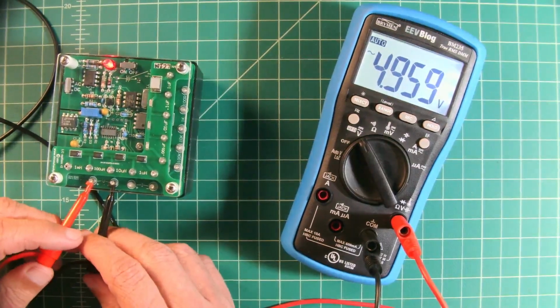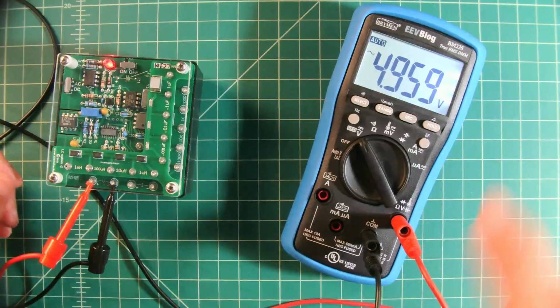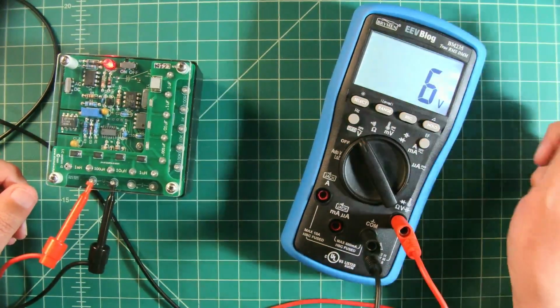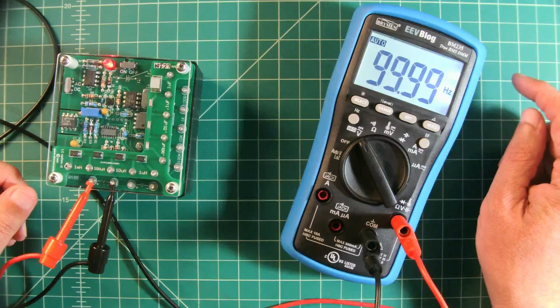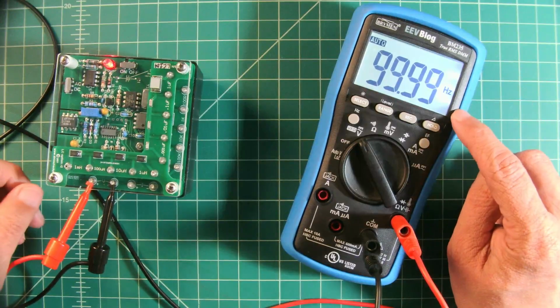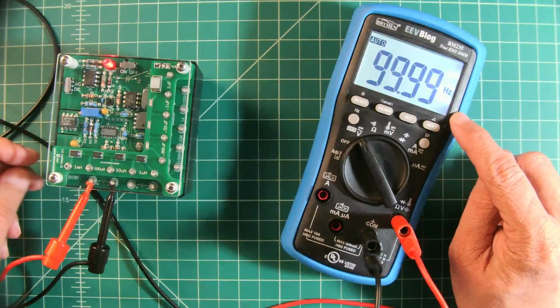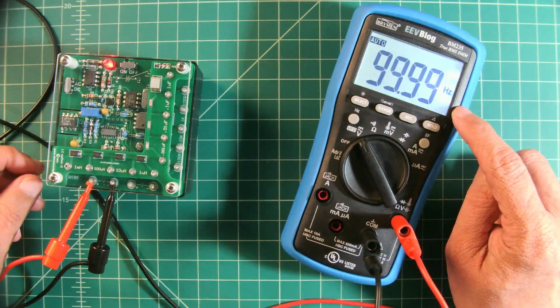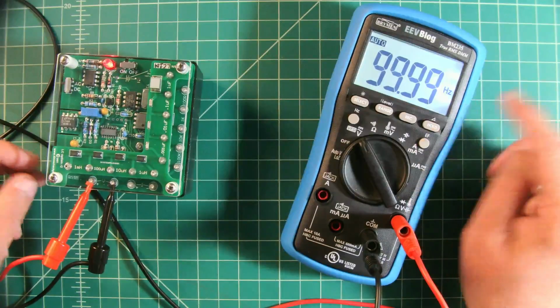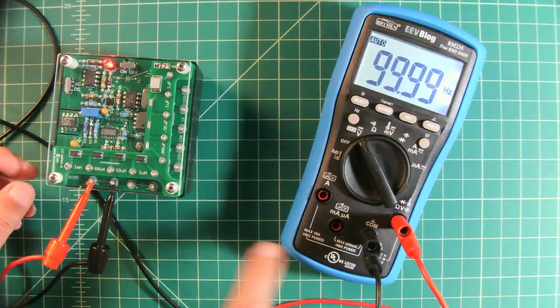Now, one of the things that this can do is you can test your hertz. And so when I switch this over, you can see, according to my sheet, I should be at 100 hertz. And we are at 99.99, which is in spec, according to this meter.